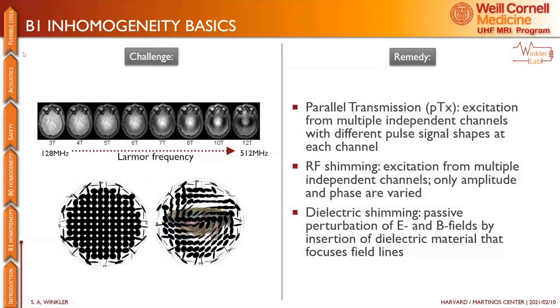So the challenge here is that as you go up in field strength, not only does the magnetic field strength go up, but the Larmor frequency is directly proportional to the field strength. So at 3T, you might have 128 megahertz, but at 7T, you're actually on the order of 300 megahertz. And what that means is that the wavelength in tissue shortens dramatically. So you're now on the order of maybe 13 or so centimeters in tissue for the wavelength. And that means that a minimum or a maximum of a wave can occur just inside the head, for example. And that's why you see here a minimum as a dark spot, a maximum as a bright spot, and so on.